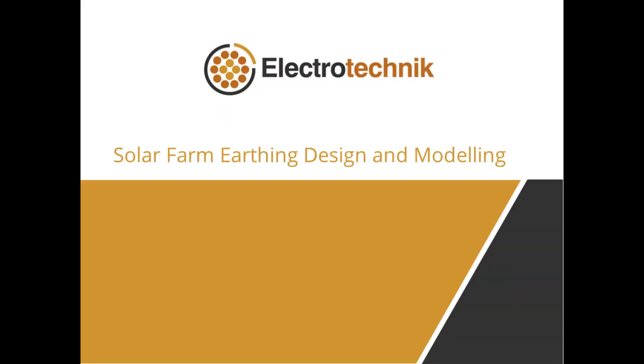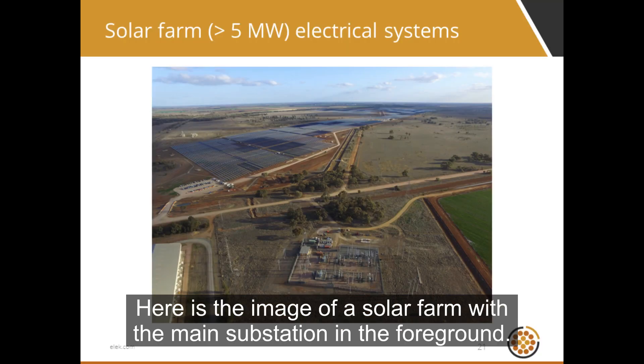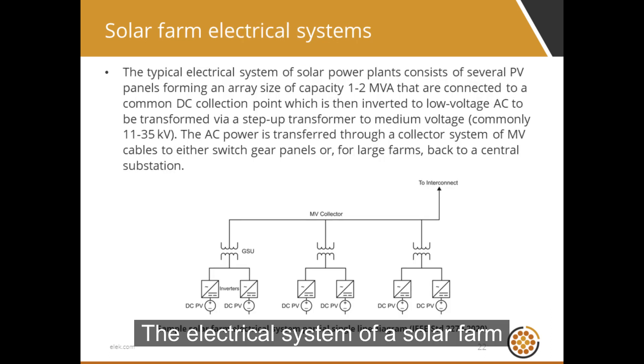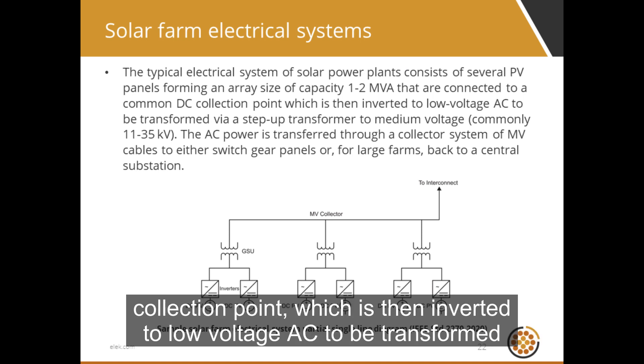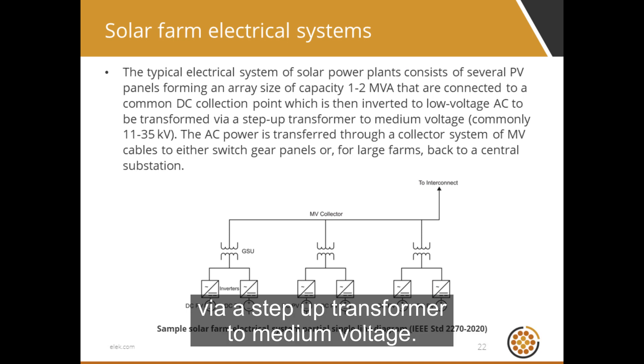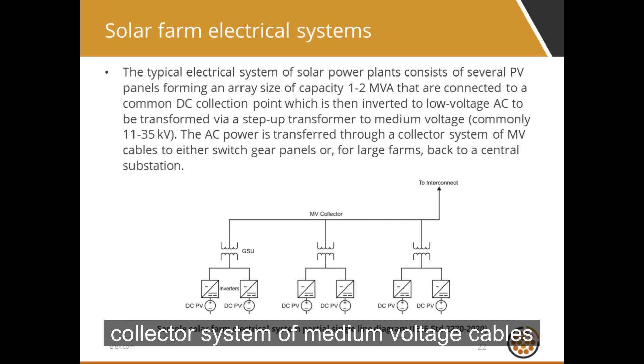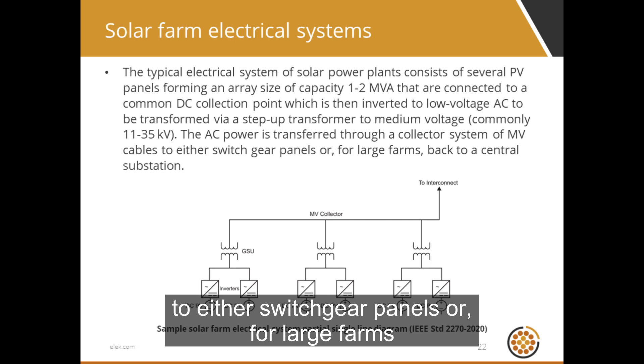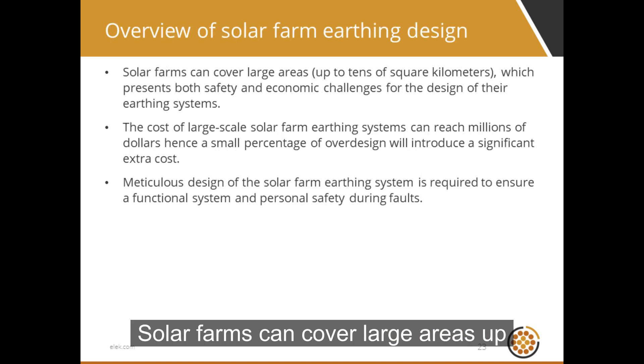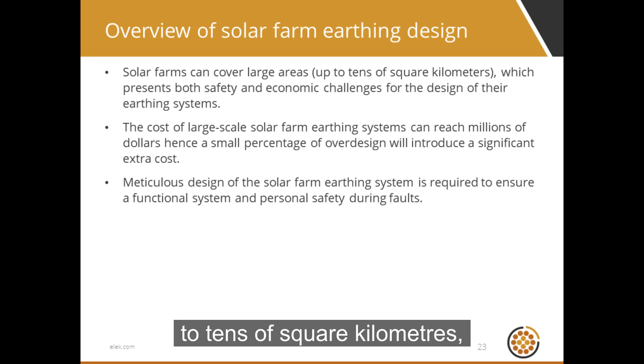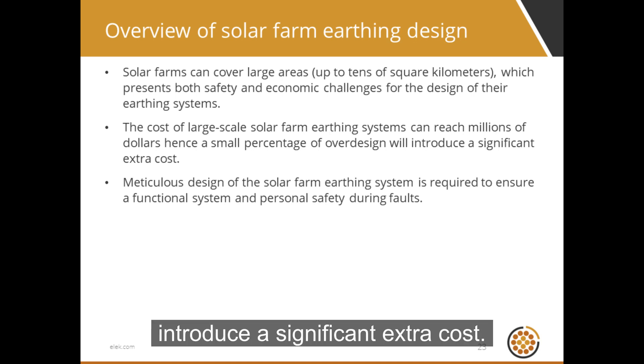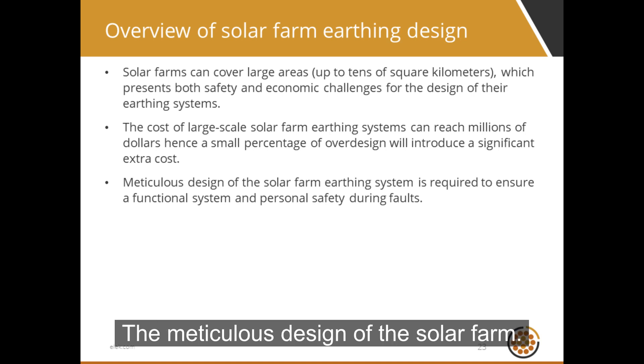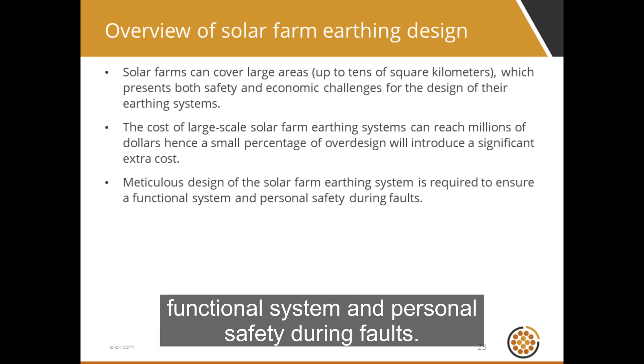Next, we will explain how to design and model earthing systems for large solar farms. Here is an image of a solar farm with the main substation in the foreground. The electrical system of a solar farm consists of several PV panels forming an array connected to a common DC collection point, which is then inverted to low-voltage AC and transformed via a step-up transformer to medium voltage. The AC power is transferred through a collector system of medium voltage cables to either switchgear panels or, for large farms, back to a central substation. Solar farms can cover large areas up to tens of square kilometers, presenting both safety and economic challenges. The cost of large-scale solar farm earthing systems can reach millions of dollars, so meticulous design is required to ensure a functional system and personal safety during faults.